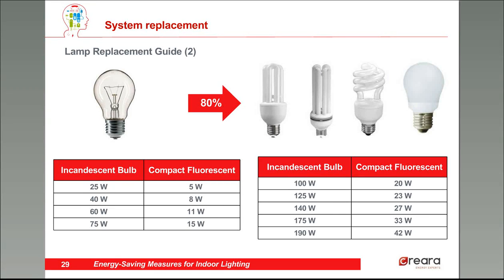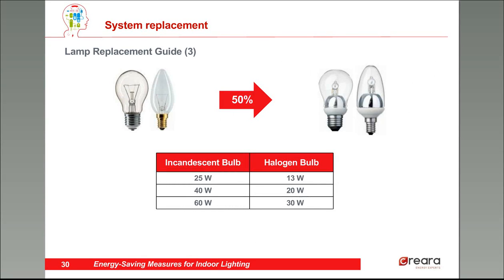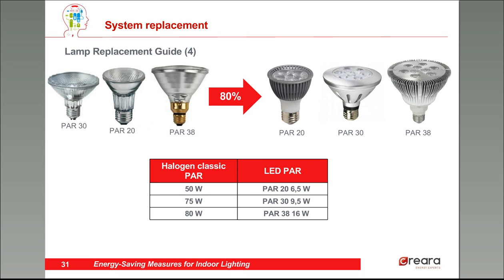From an incandescent lamp to a compact fluorescent, the savings are also huge — we can achieve 80% savings. From an incandescent lamp to a halogen bulb, the savings are also significant at 50%, and we maintain the quality because halogen is also an incandescent technology, so we can maintain the quality of light. These halogen lamps can also be replaced by LEDs, saving 80% of energy consumption. Looking at the table, we have 50 watts against 6.5 watts, or 75 watts against 9.5 watts — that's 80% savings.